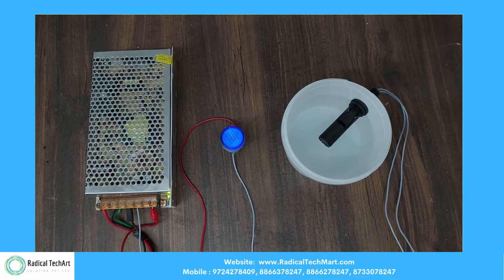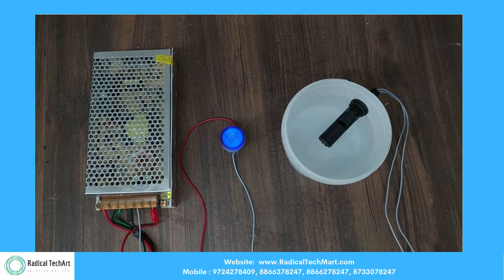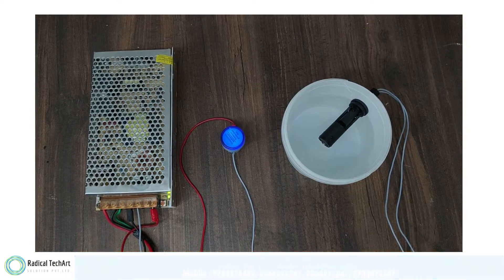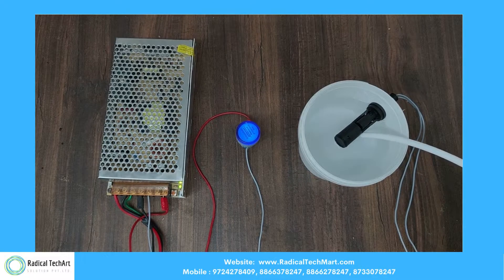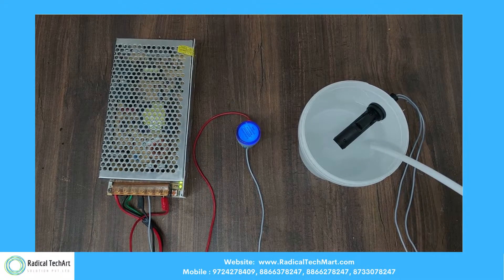We have fixed this float switch as a low switch, so when you pour water into it, the float switch goes upward and indicates. When you decrease the water level, the indicator will show the light so that we can understand the water level is on the low side.